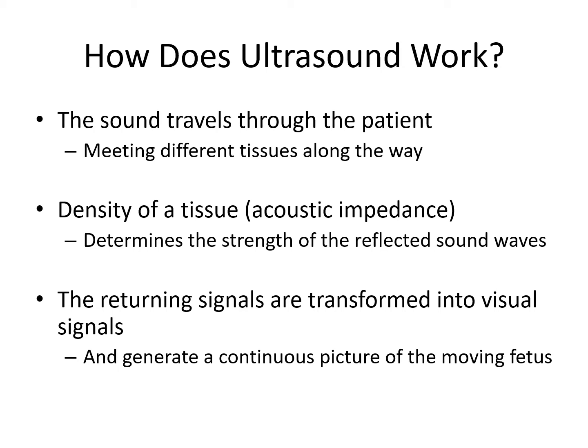The sound waves travel through the patient and meet different tissues along the way. Tissues have different degrees of density and hence different impedance or blockage of the sound waves. Something more dense such as bone will reflect the sound waves much more strongly than something such as liquid like amniotic fluid. Bone reflects brightly because of its high acoustic impedance and high reflectance of sound waves, whereas fluids appear as black on the ultrasound screen.